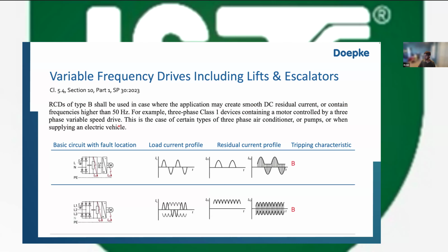This is basically what we have in most of the installations. You have a variable frequency drive and it is a class 1 device, so it has a connection for the protective conductor. And also other examples are three-phase air conditioner pumps, etc. What happens, you see, is that when you have a fault within these devices, the type of fault current is not a sinusoidal alternating current. It is a chopped up waveform that is generated. How is that waveform generated?